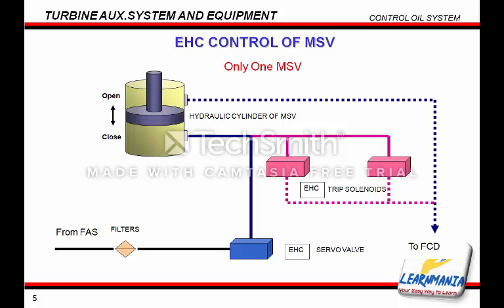The cylinder is reopened by the turbine reset signal. If there is only one MSV, the test valve will be a servo valve. If an additional valve is present, this will be a solenoid valve. However, for combined type MSV-CVs, as CV warming does not need to be carried out, a servo valve is not necessary.